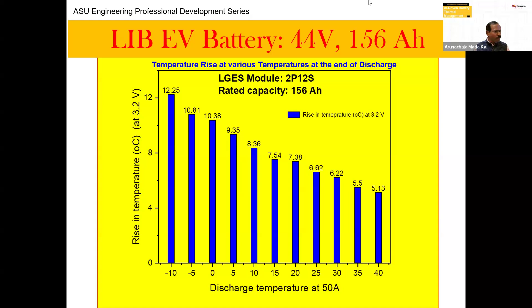So that's again very important, that you need to manage the temperature of the battery pack in the sweet spot, which is almost about 10 degrees at a lower temperature, because even at lower temperature, say 15, this is at the end of discharge. So maybe within half an hour or within 1 hour, it's always going to increase the temperature by maybe 3 to 5 degrees Celsius in the pack.